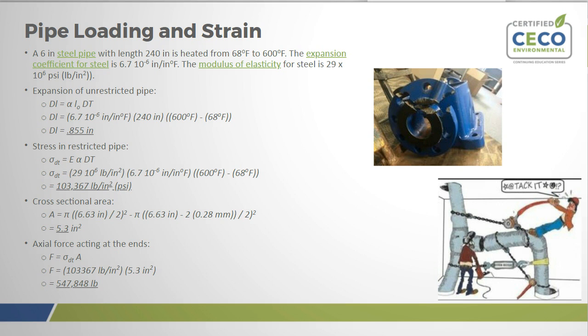When we started looking at it, it was a 6-inch pipe about 20 feet long, 240 inches. It was heated from 68 degrees, which we considered ambient temperature at the time, to about 600 degrees F. The expansion for steel is 6.7 times 10 to the minus 6 inches per inch per degree F, and the modulus of elasticity for steel in this case was 29 times 10 to the 6th, as always. So for an unrestricted pipe, if you do the math, you find that the 20 feet of pipe actually grows 0.855 inches when heated from 68 to 600 degrees F.